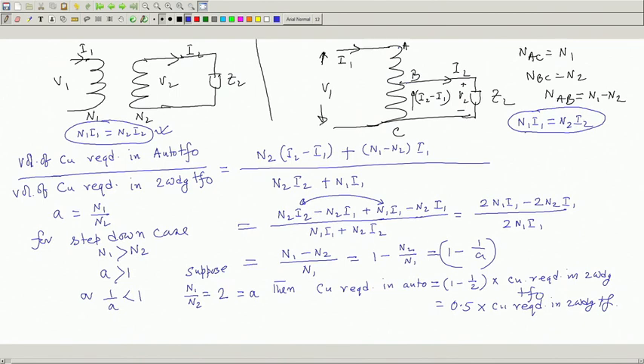So if you require 10 kg of copper to make a two winding transformer, you need only 5 kg to make an auto transformer. You save copper, it looks like. Savings of copper can easily be calculated by taking the difference of these two, which I won't do here.